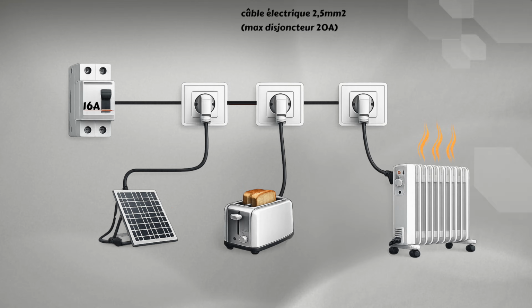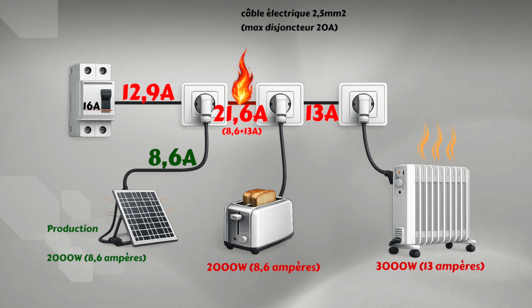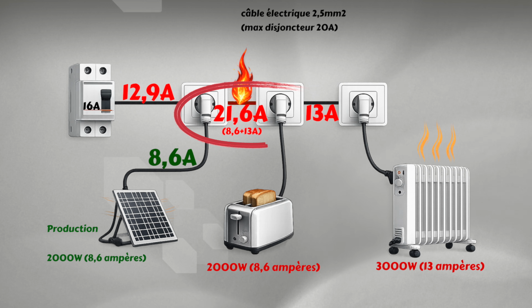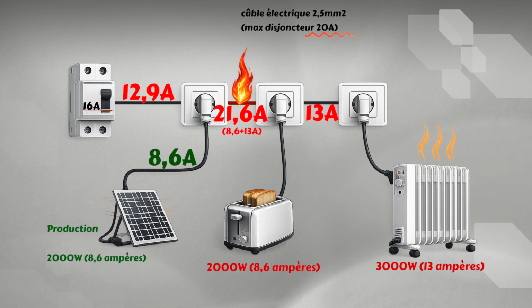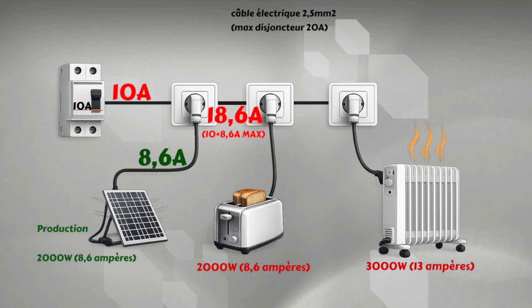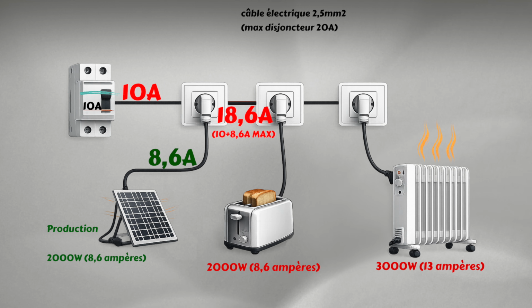Now, there's one important detail to keep in mind for safety. If your solar panels are connected to the same circuit as other appliances, you need to properly size the circuit breaker according to the solar panel power, so you don't exceed the cable capacity. As you can see here, if the breaker rating is too high, part of the cable could exceed its thermal capacity. That's because the solar panels are adding power into the circuit inside the section protected by the breaker. By lowering the breaker rating according to the panel output, you make sure the cable never carries more than it can safely handle. Here's an example of proper sizing to protect the circuit from overload.